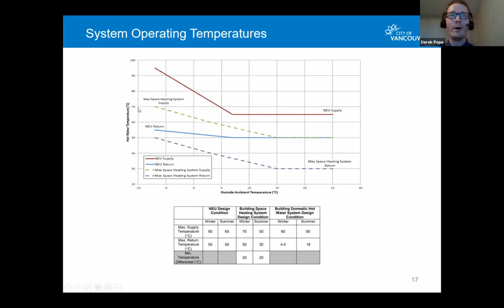On the domestic hot water side of things, the standard or code here is that hot water be stored at 60 degrees Celsius in a storage tank within a building. That's why we can never come below 65 degrees Celsius supply - we need to be able to heat the building's domestic hot water to 60 degrees Celsius.